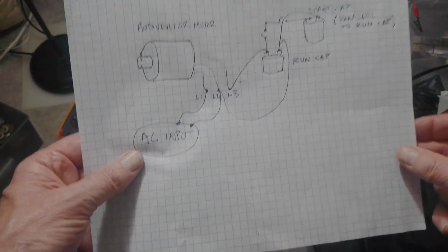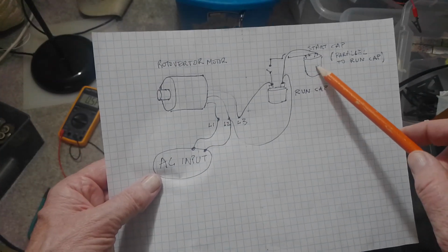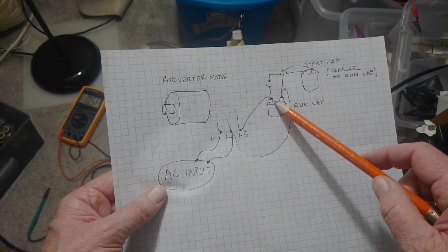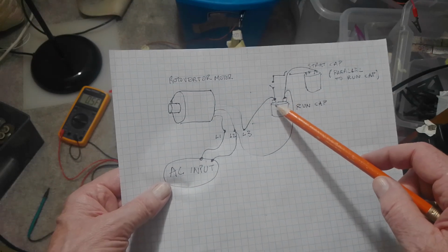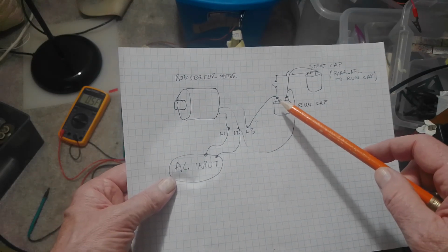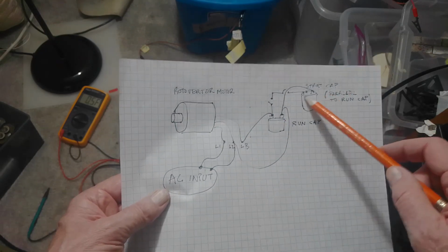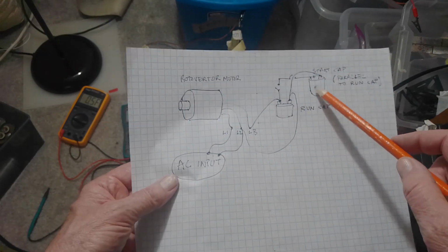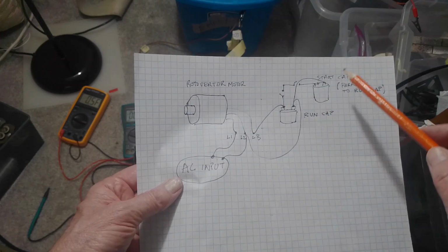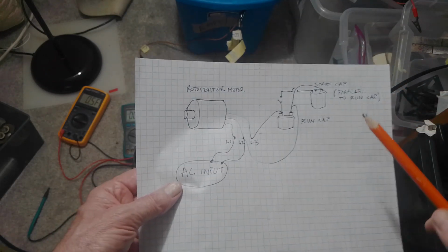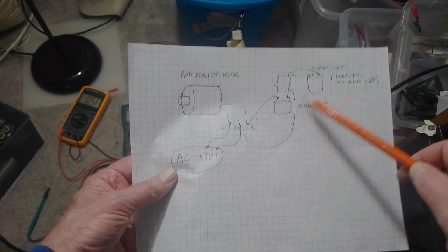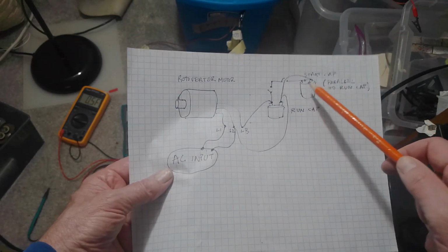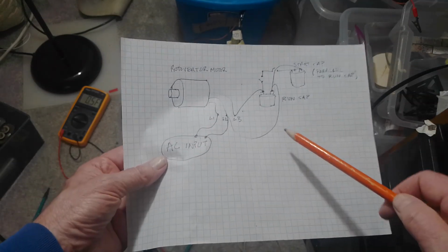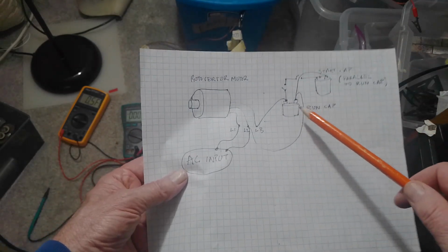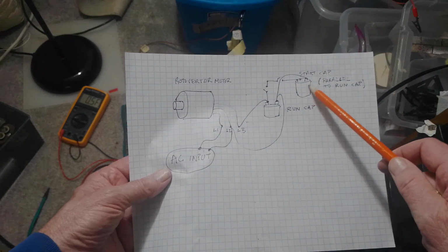Just for grins, the way you start it up is you put a start cap in parallel to the run cap. It'll give it a lot of juice and it'll start from stop. When it gets up to speed, you disconnect the start cap. You want to have this maybe 75 UF. Actually, this motor I have now is so efficient, I only need an 8 UF start cap just to get it going from stop. But usually you have like a 50 to 100.